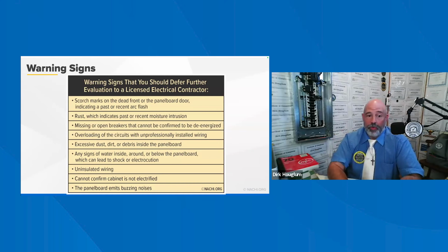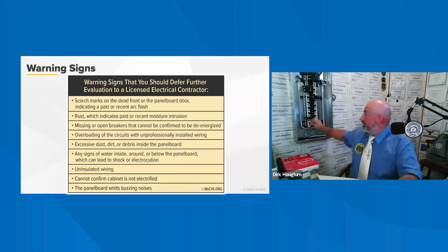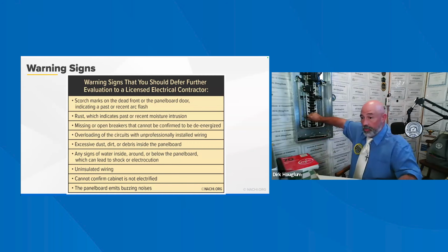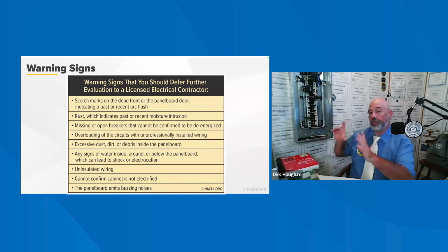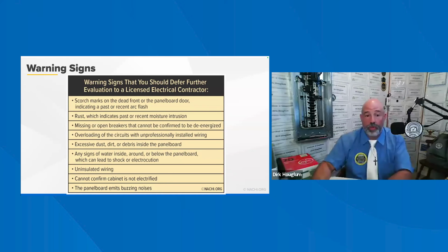Uninsulated wires, make sure you call those out. And if you cannot confirm the cabinet is not electrified, or the panel board emits a buzzing sound. I've had that happen a few times where a circuit breaker was actually humming, and when I did my thermal reading, I could actually tell which one it was.